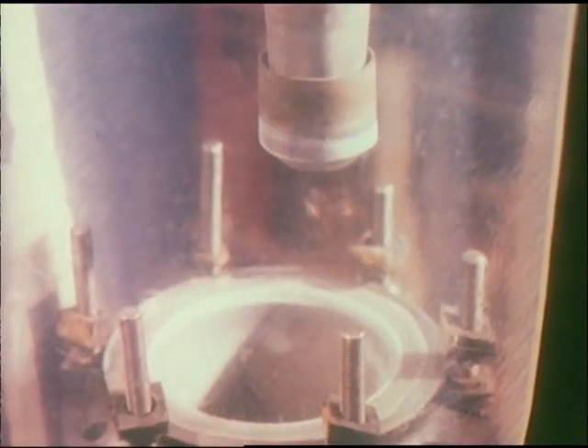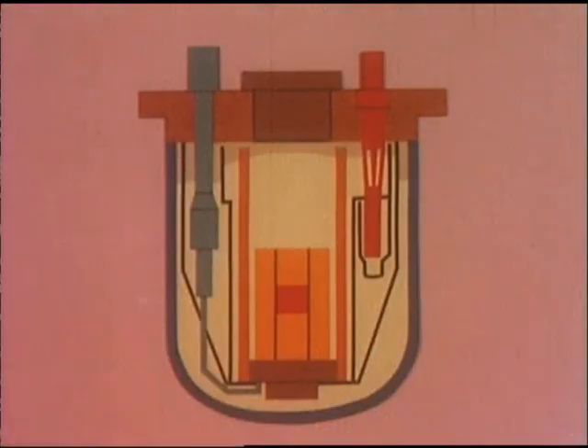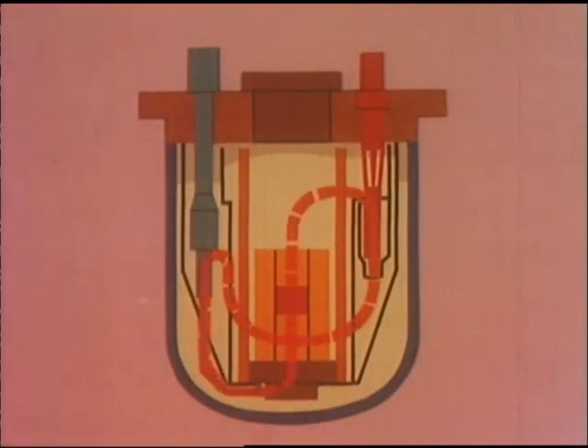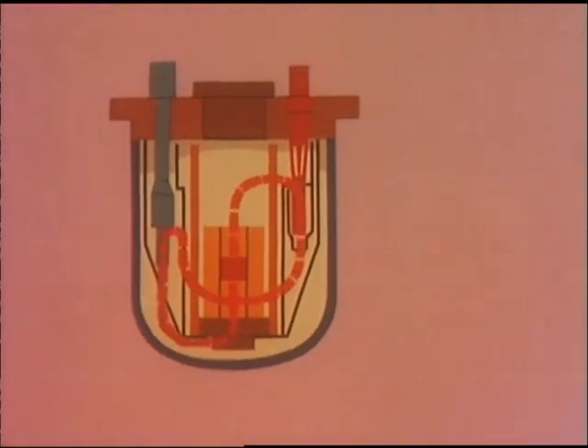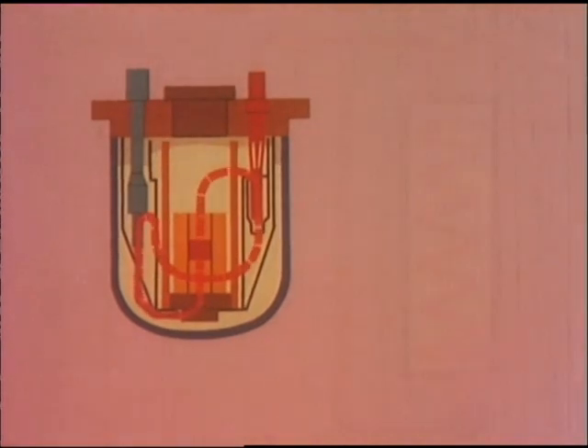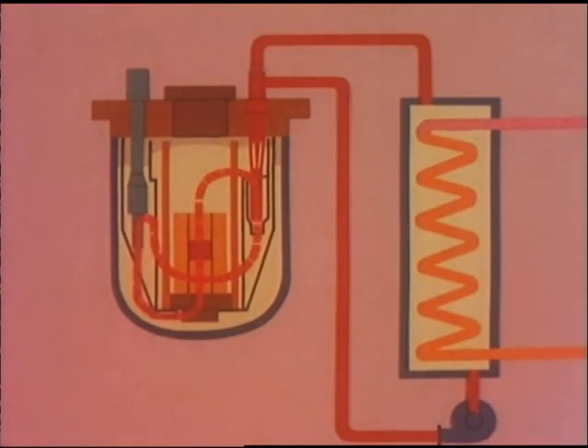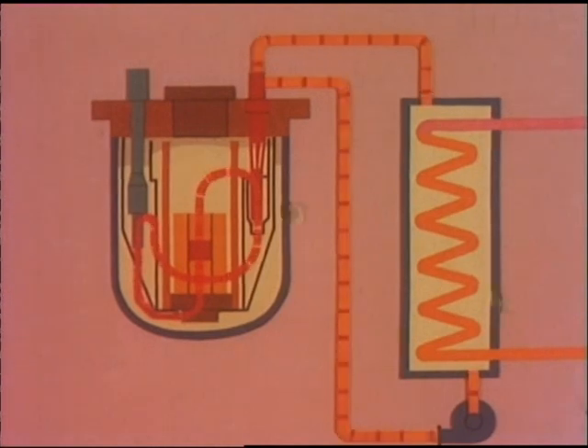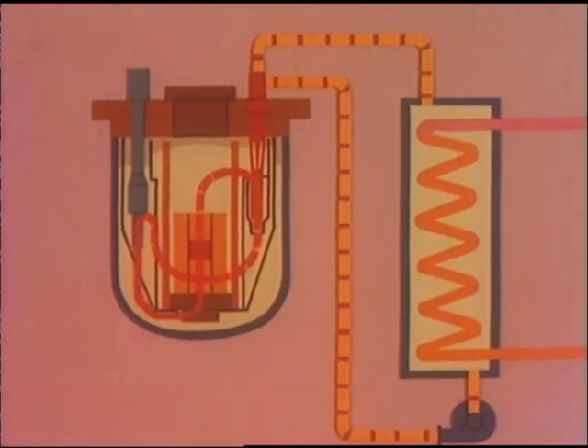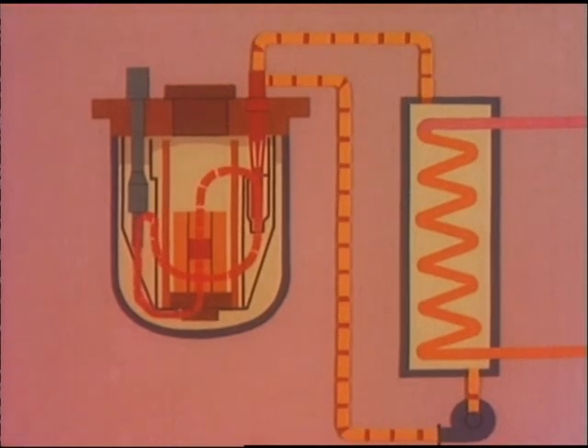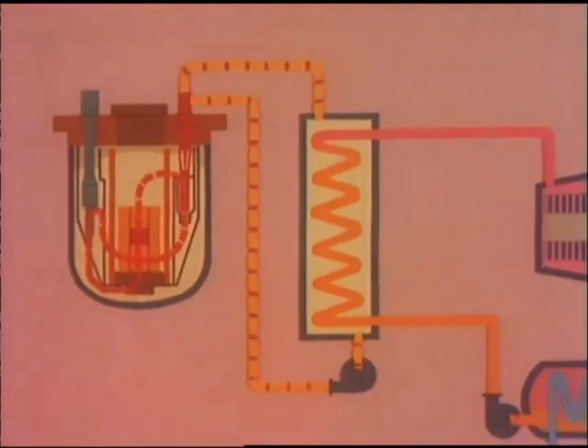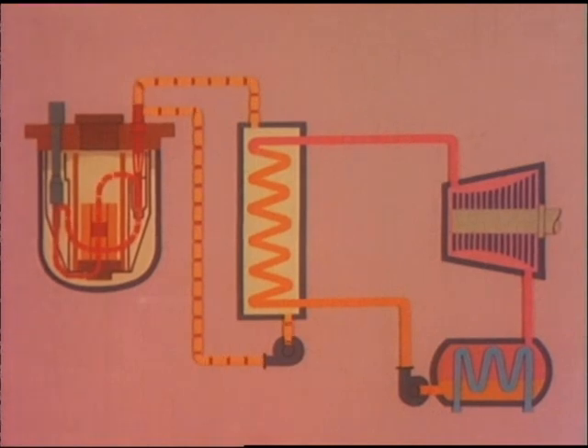The heat transfer system adopted was as follows. In the primary circuit, liquid sodium flows continuously between the reactor core and the intermediate heat exchangers. These form a link with the secondary circuit, in which an independent sodium supply picks up heat and delivers it to the steam generators or boilers. The steam produced in the boilers is fed to the turbines, condensed, and returned to the boilers in the usual way.